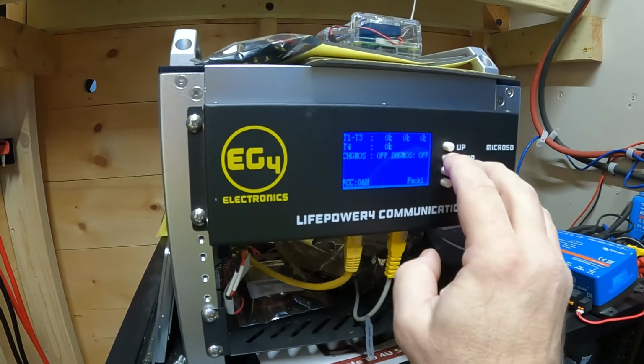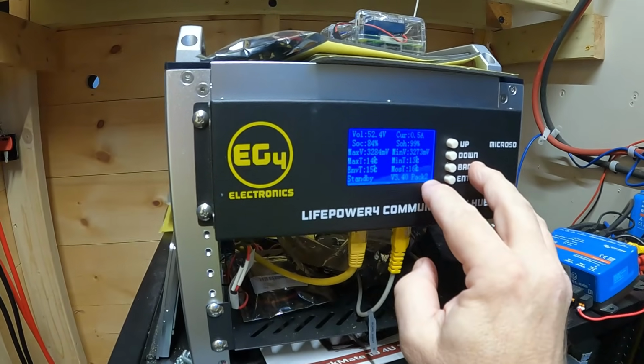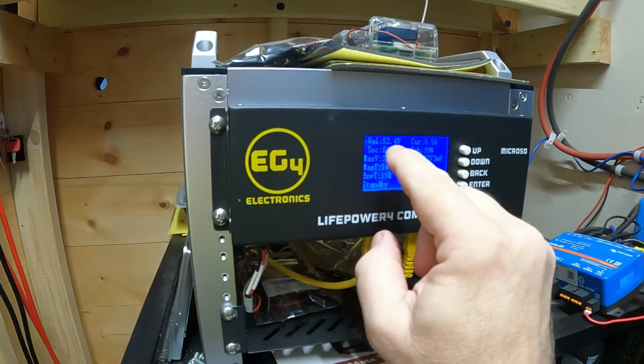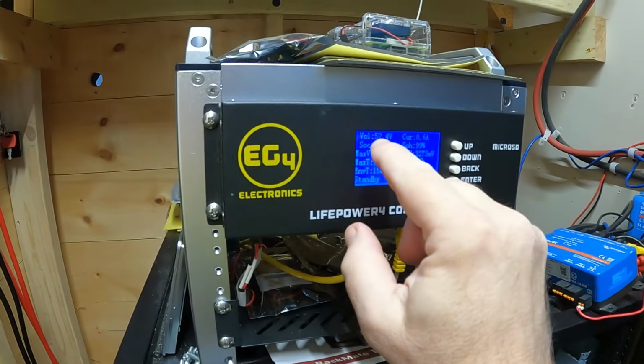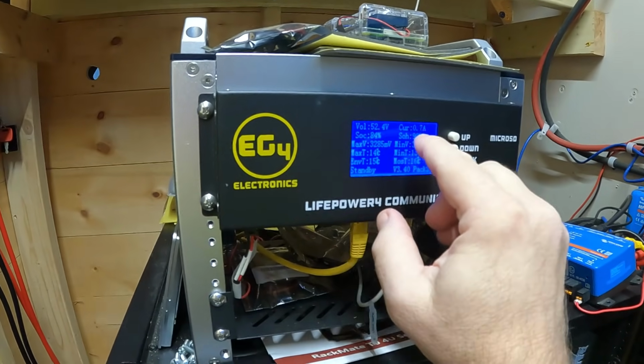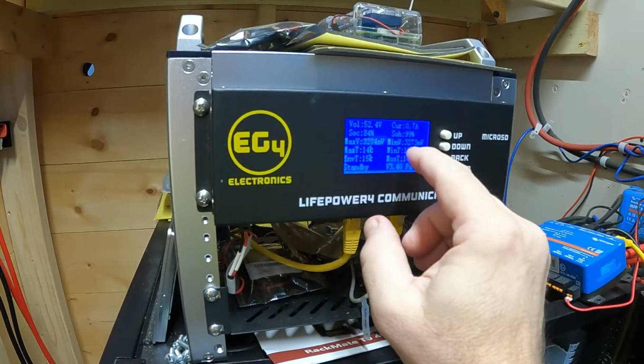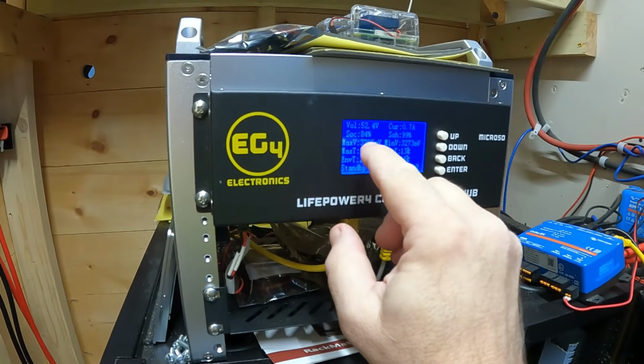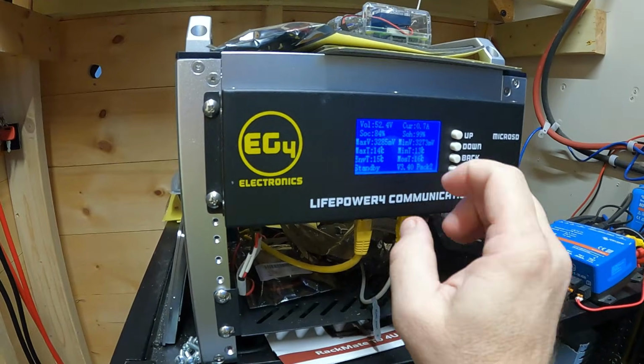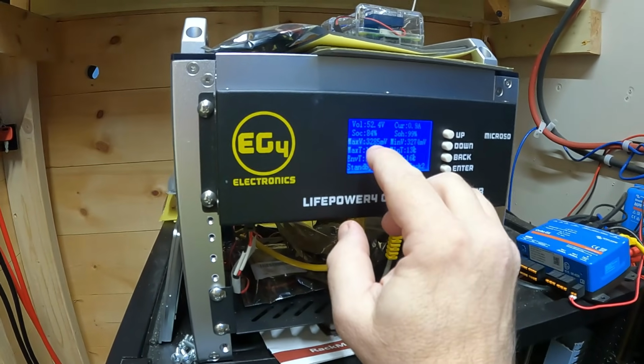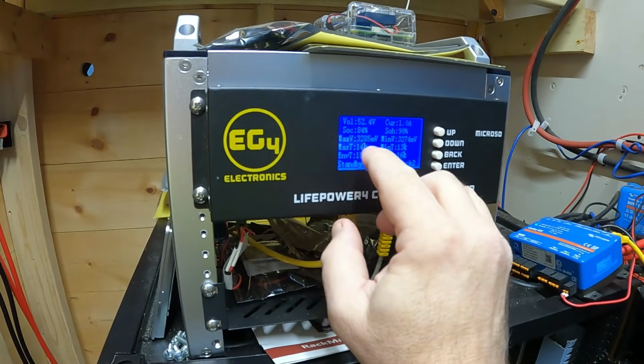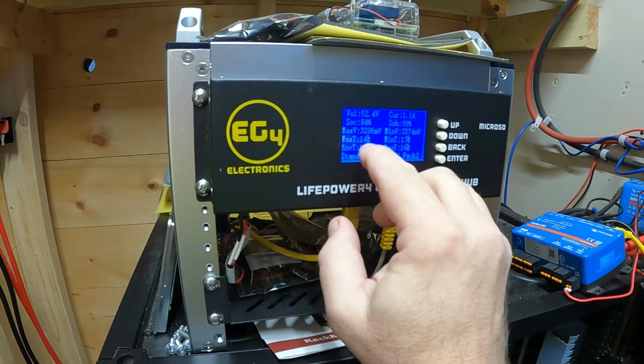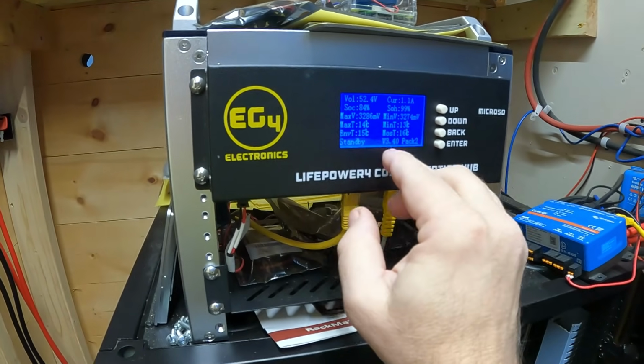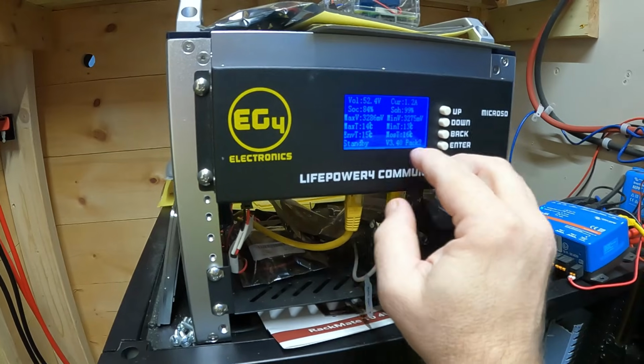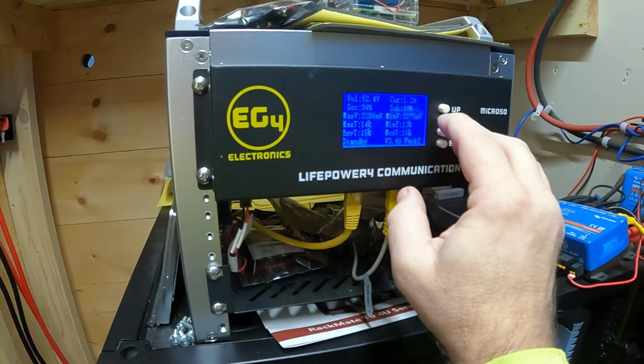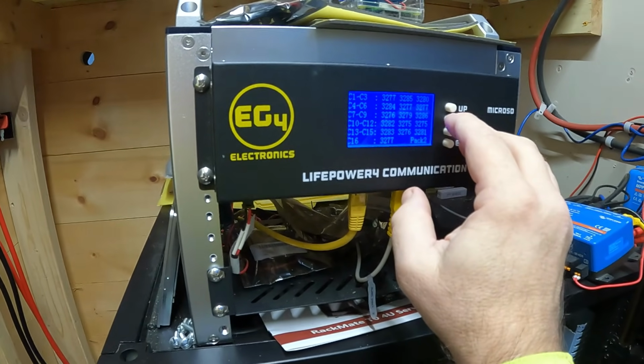Cell voltages. Pack number 2, which is on, the voltage of that pack is 52.4. It's got 0.7 amps coming in. It is getting charged by solar. It's at 84% state of charge, 99% state of health. The highest voltage of any cell is 3285. The minimum is 3274. Here are the 4 temperature sensors in there, and I'm on version 3.4 of the BMS. So that's pack number 2.